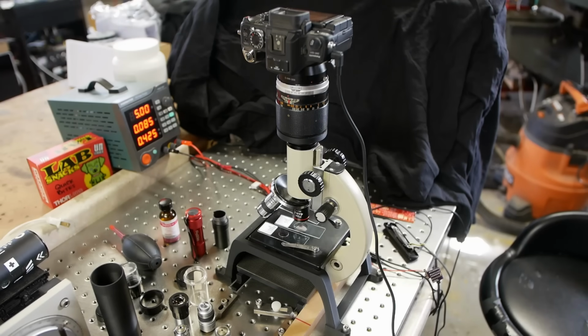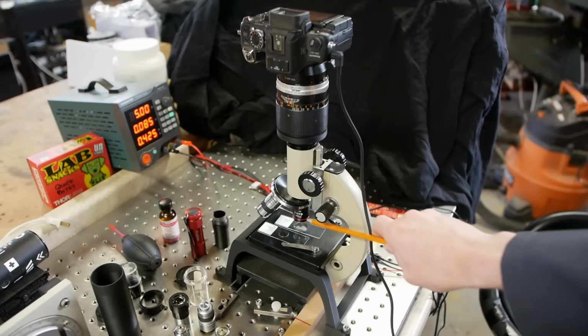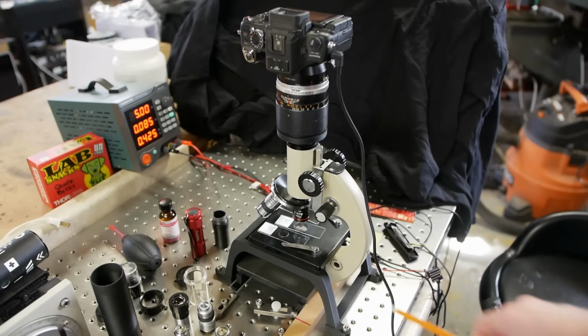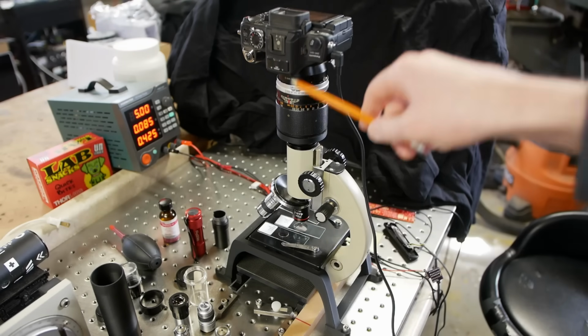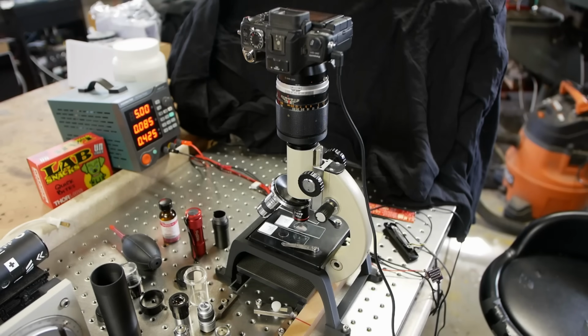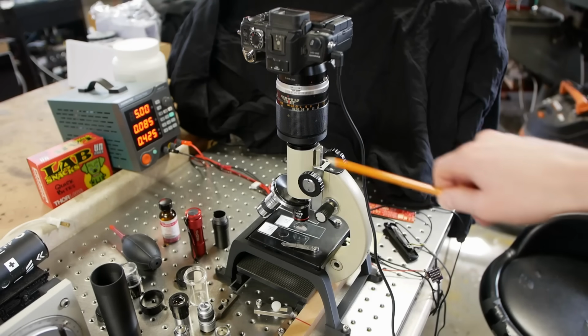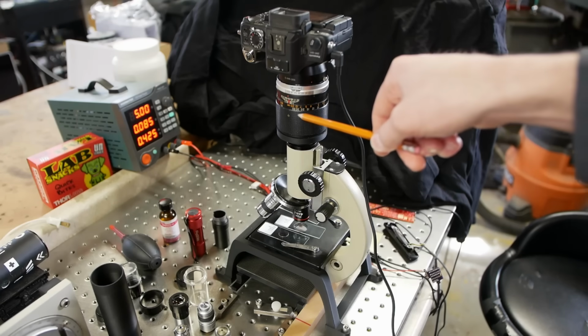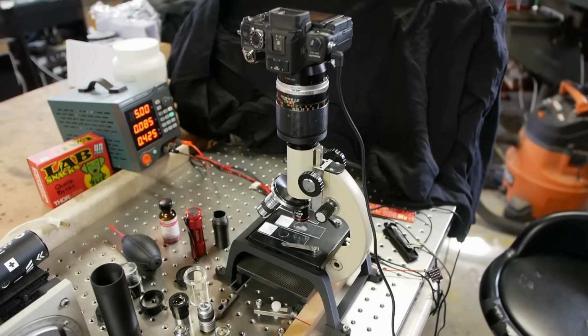This whole process works best with a 4x or a 2x microscope objective. And if your objective has an infinity sign on it, that means that the optical aberrations of that objective are best corrected when the objective has infinity space behind it. In other words, your camera is infinity far away on this side. But since that's pretty impractical, we've got to add another lens called a tube lens to focus this infinity light down to the focal plane of the camera.